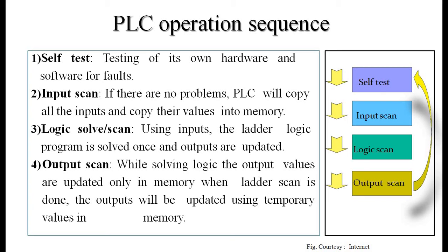This cycle continues to work. Once the output scan is complete, it will send highs or lows to the respective output devices, and then it will start for input scan again. Likewise, it will continuously update the inputs, solve the logic, and update the outputs. This is called the update-solve-ladder-update cycle. Continuously this cycle will run, and there will be changes in the output according to changes in the input sensors. This is the operational sequence for a PLC.